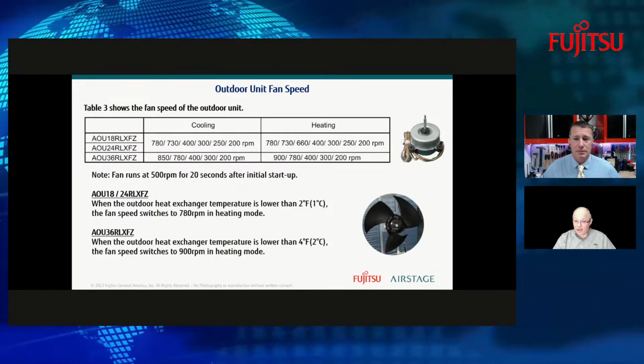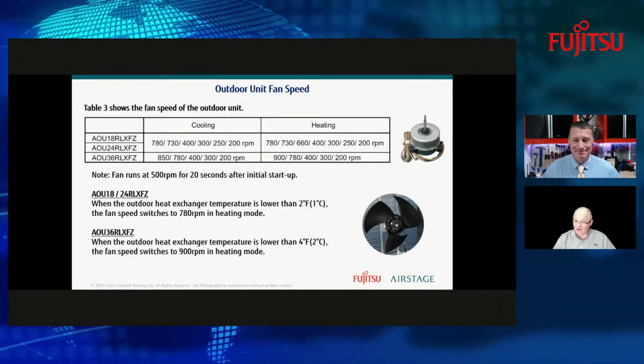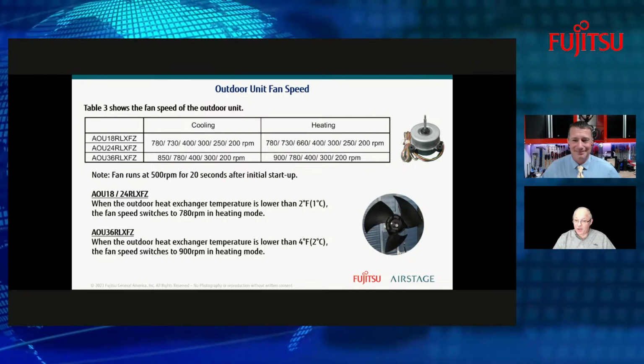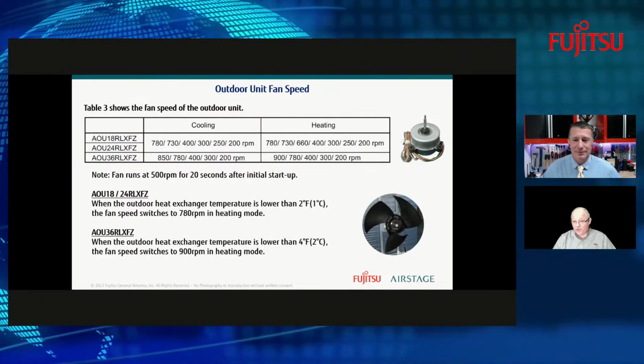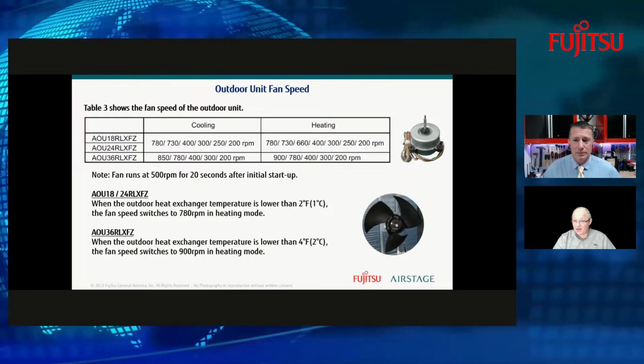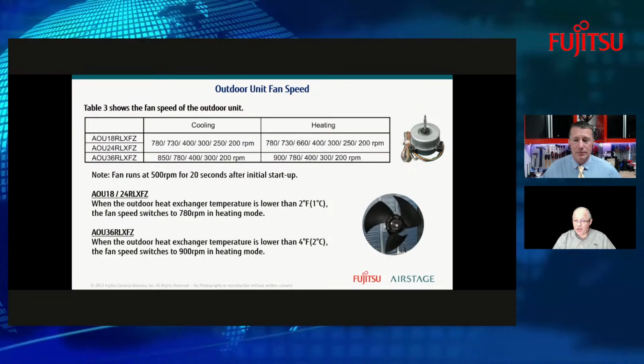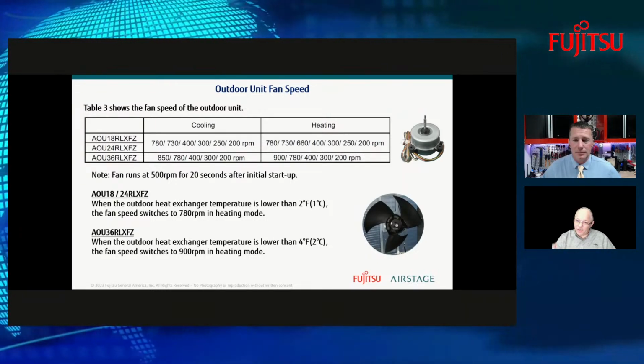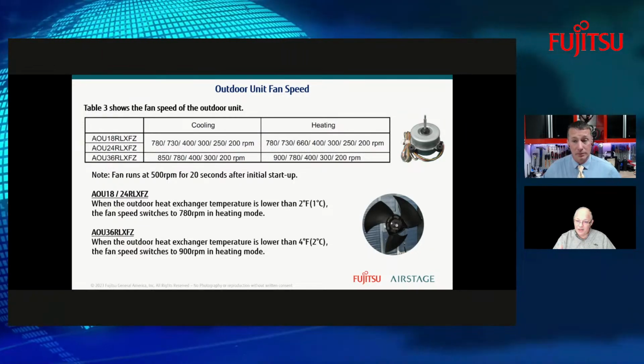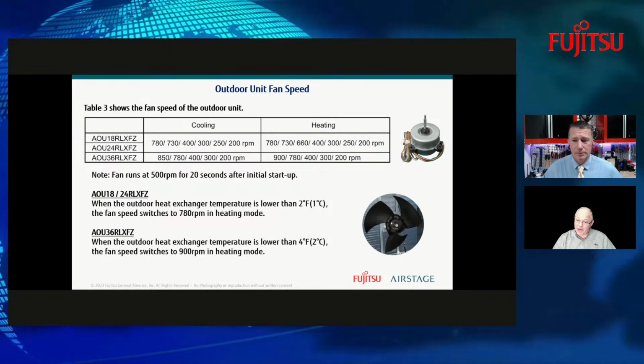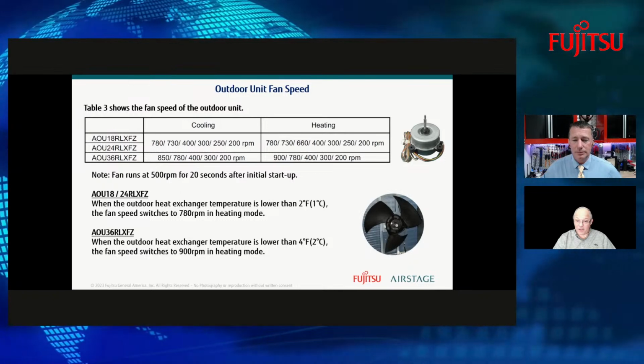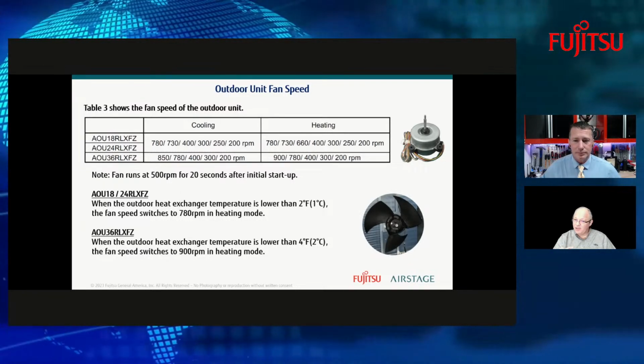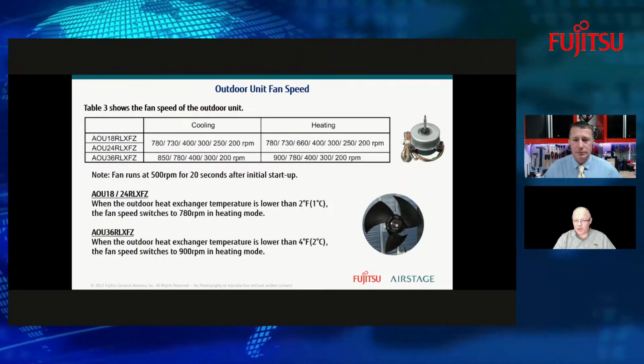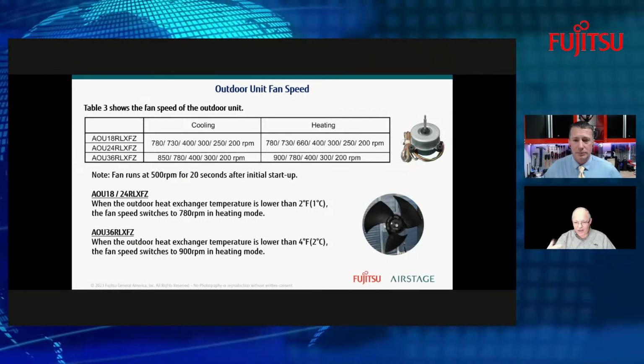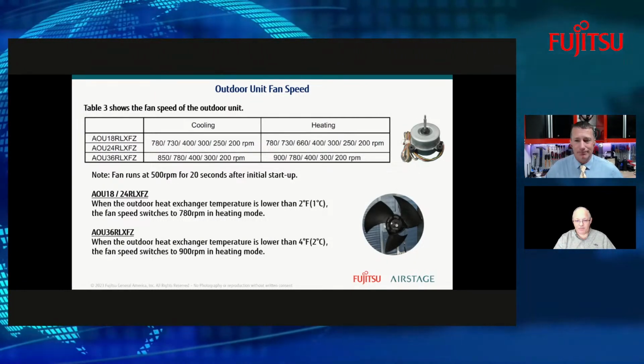So again, it's still looking at the temperature outside and it's looking at the temperature inside. So as the outdoor fan's running, if the temperature goes up outside, then that's going to change how the outdoor unit's getting rid of the heat that's hitting that heat exchanger. So it's naturally going to pick up some heat from the outside temperature going up. The system's going to see that, and then it's going to make a change to make that fan go a little bit faster to get rid of the heat. Okay.